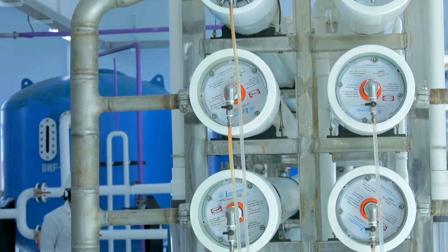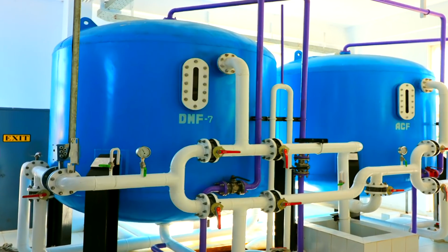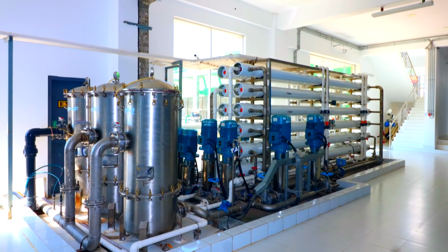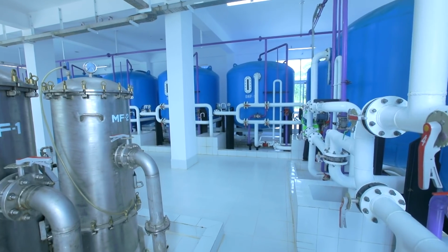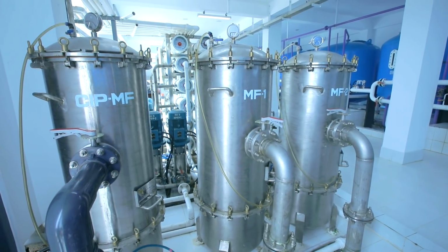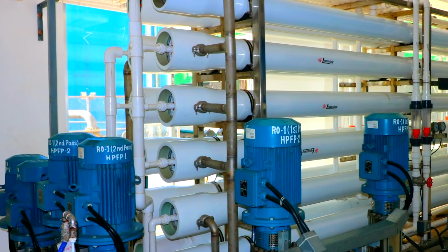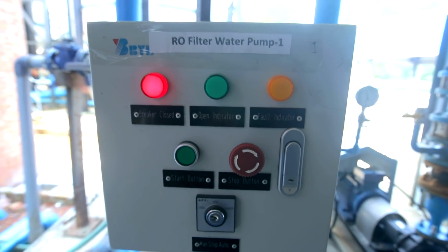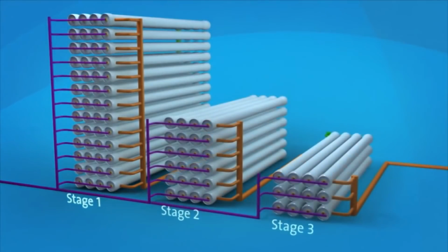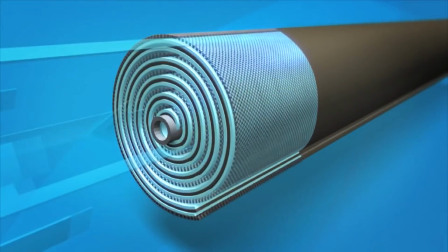The pre-treated filtered water is refiltered by passing it through another set of 2 series connected media filters. This double-passed filtered water is fed to the RO unit via a micron filter. The micron filter elevates the degree of cleanliness of RO feed water, removing the colloidal solids. The first and second stage RO eliminate almost all the dissolved minerals. Further passing the water through the third stage eliminates the residuals. The third stage RO polishes the demineralized water quality to a stringent level.